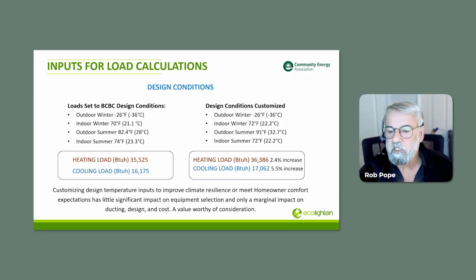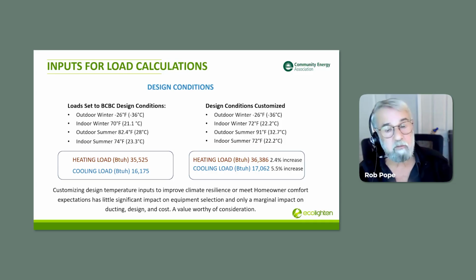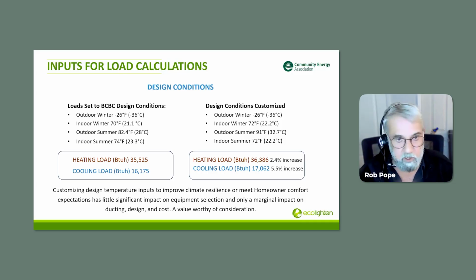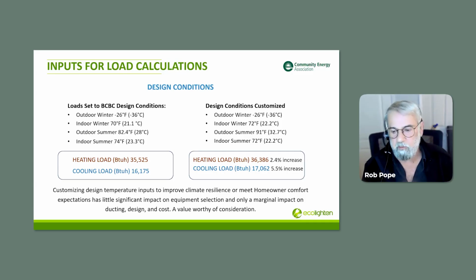The load went to 36,386 from 35,525, not even close to 1,000 BTUs increase on the cooling load. It was a 2.4% increase on heating, 5.5% increase on cooling. So what we're demonstrating here is that to do these things really has a marginal impact on the load, on the ducting design, total cost and budget, choice of equipment, and very little impact on implementation of the system, compared to satisfying the comfort of the homeowner with resilience and expectations being met.